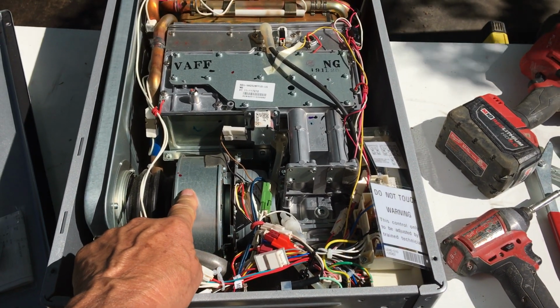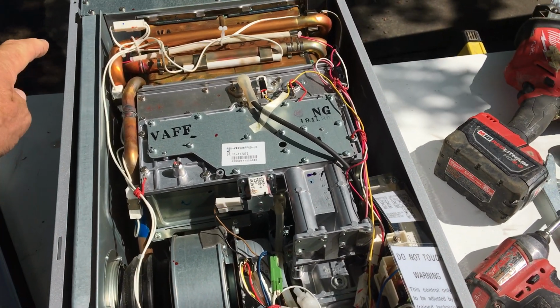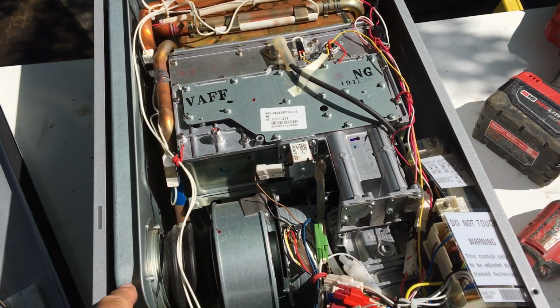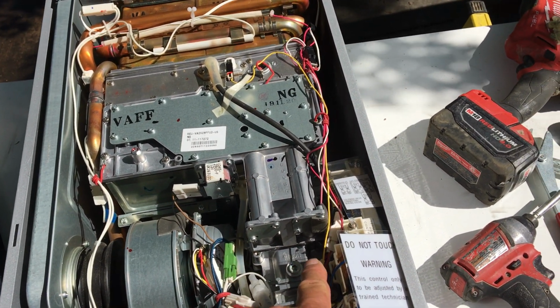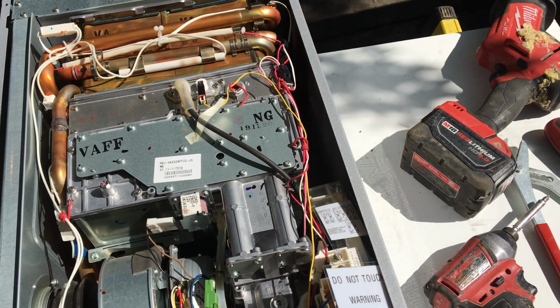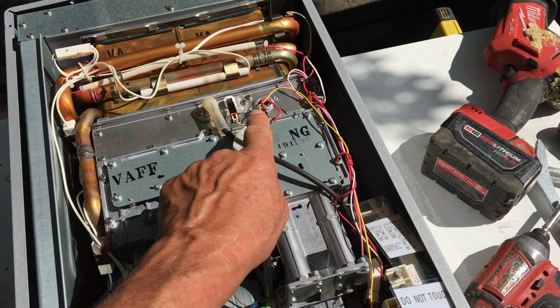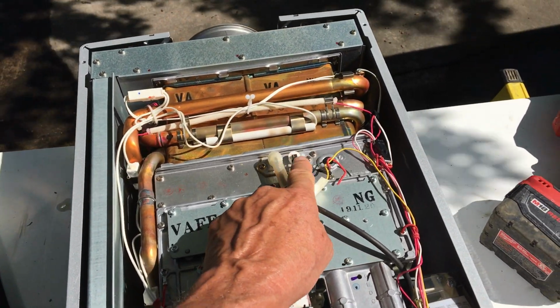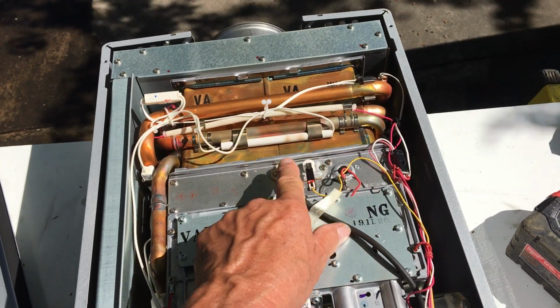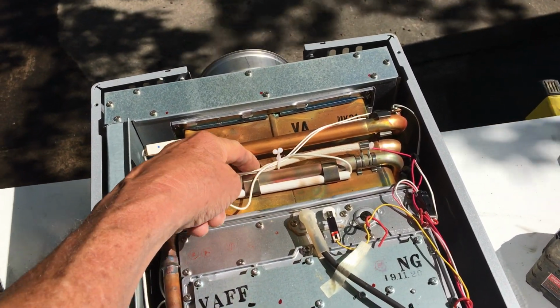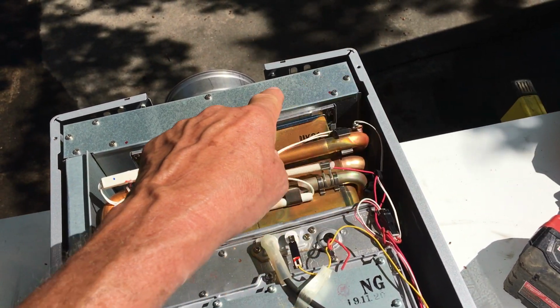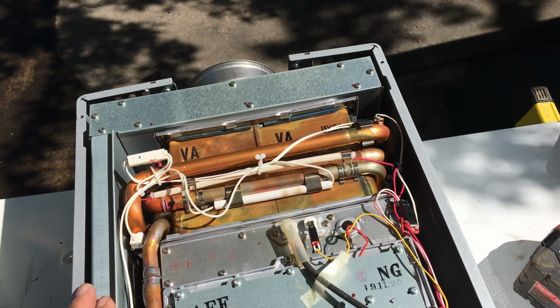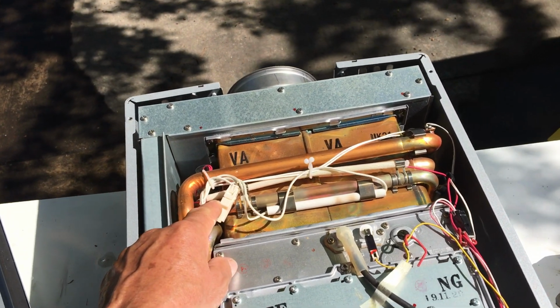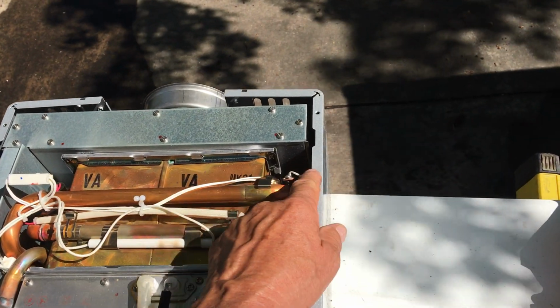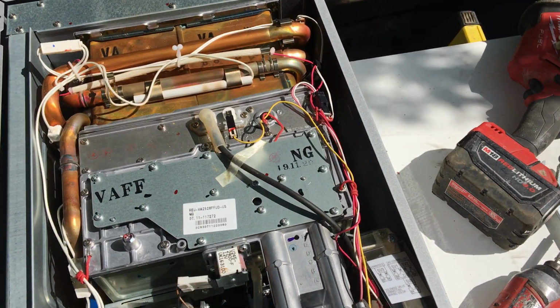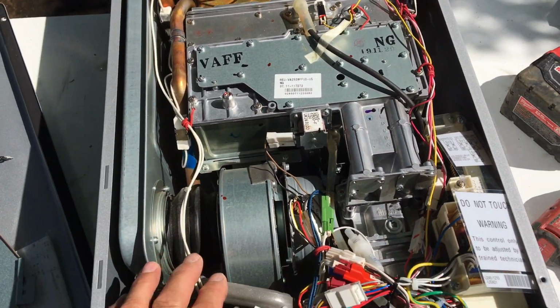Inside you have a blower, which I think is bringing fresh air in through this, coming through the blower, mixing it with gas, and then injecting the gas and air mixture up into the boiler. This looks like an igniter here, so it probably ignites that fuel air mixture, and then here's the heat exchanger where you have the water flowing through some sort of heat exchanger radiator assembly, and then of course you have various sensors, safeties, who knows what all that stuff is. But at any rate, that's basically how this thing works.